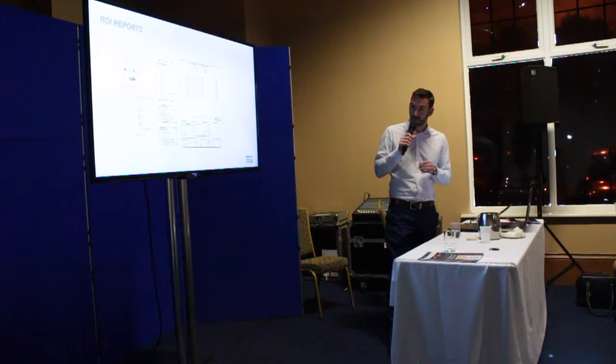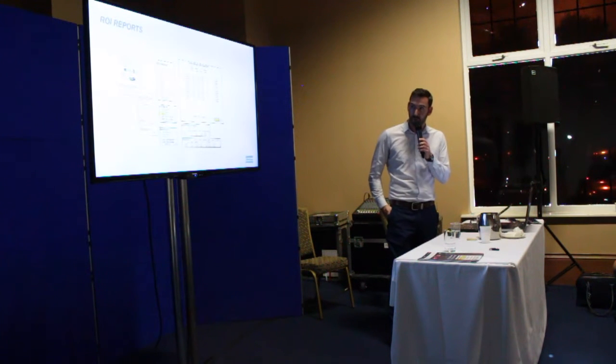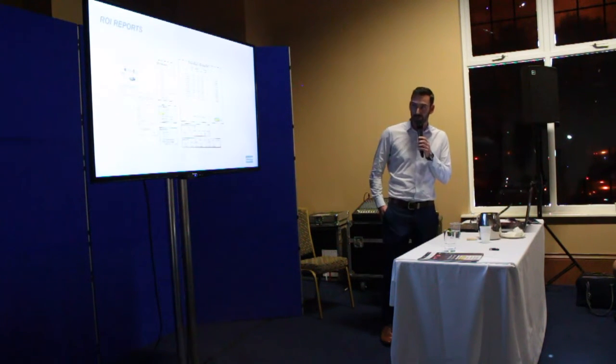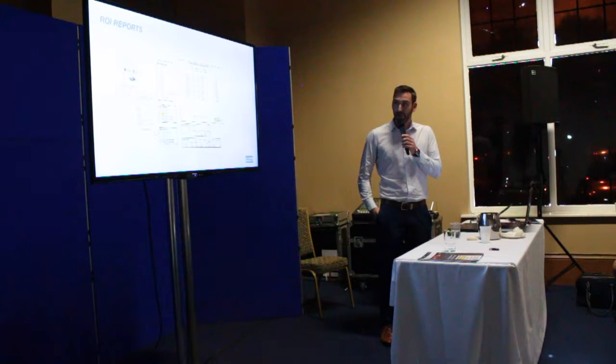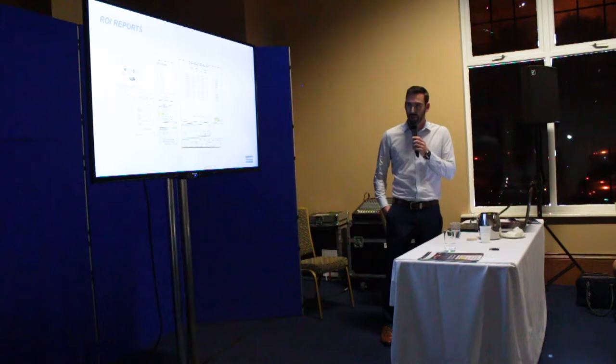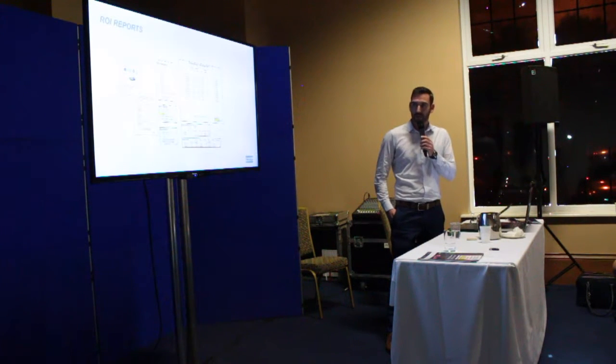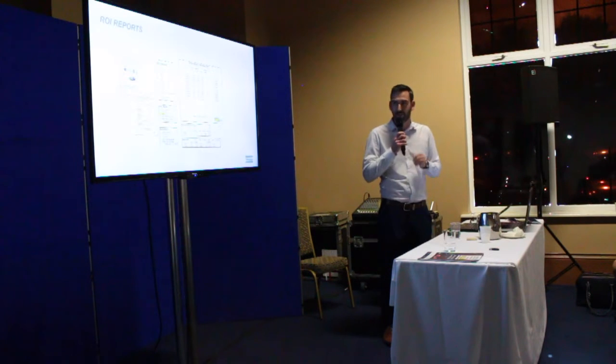As you can see from the one on the screen, this is, as they say on TV, one I made earlier. This is an actual customer's return on investment report with their details removed. We've taken a look at their bottled cost analysis, and you can see we worked out that they were paying €1.91 per metre cubed. Now we've designed a high pressure system of 300 bar to give them a cost of 52 cents per metre cubed from our system, and a return on investment of 31 months.